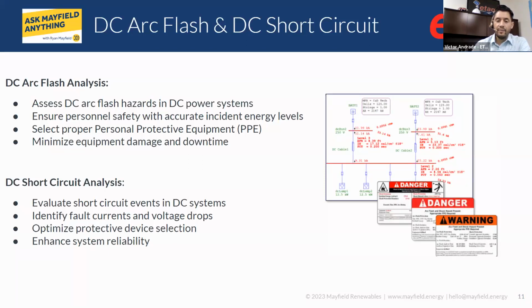Now, the importance of understanding what an Arc Flash study is and what these labels are is the following. This is mainly just human safety. So Arc Flash is important because of human safety. We have had many different incidents. We've heard of many different reports over the years of, for example, an electrician opening a motor control center or a switchboard, switchgear, a panel, working on the equipment live and actually producing an explosion, what we call an arc flash.